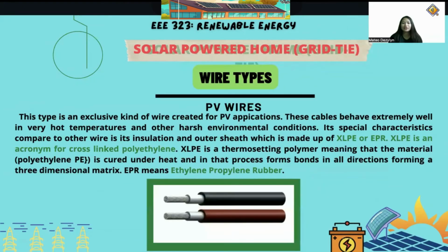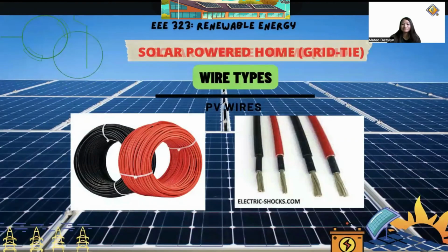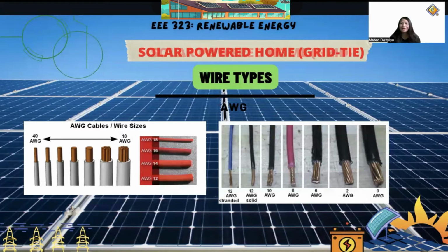Now, let's proceed to PV wires. This kind of wire is created for PV applications, and these cables also behave extremely well in very hot temperatures and other harsh environmental conditions. The special characteristic of it is its insulation, compared to other wire, which is made up of XLPE or EPR. XLPE is an acronym for cross-linked polyethylene, and EPR means ethylene propylene rubber. These are the PV wires. Also, these are the sizes in American wire gauge or AWG.